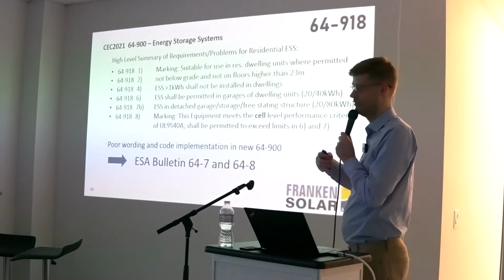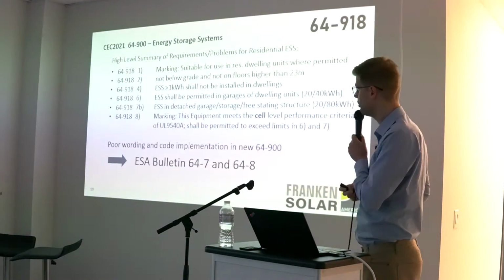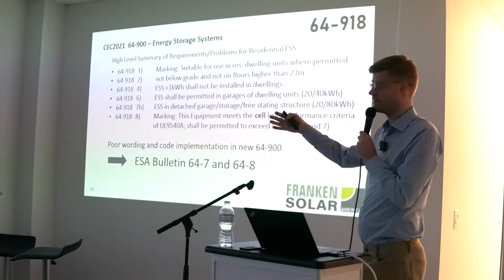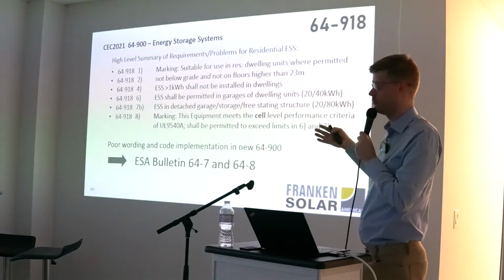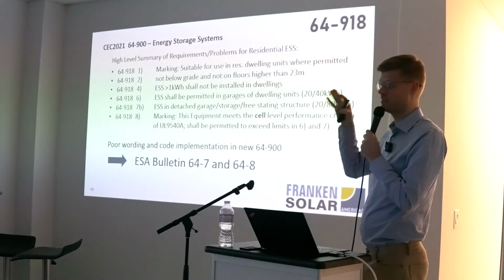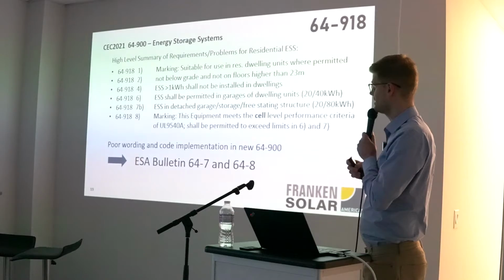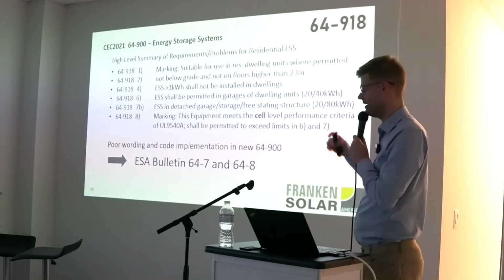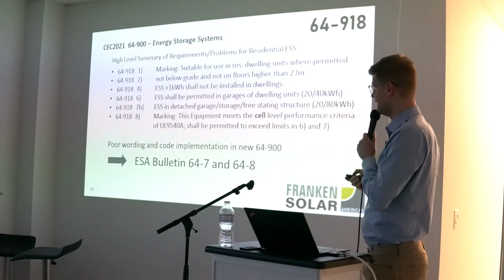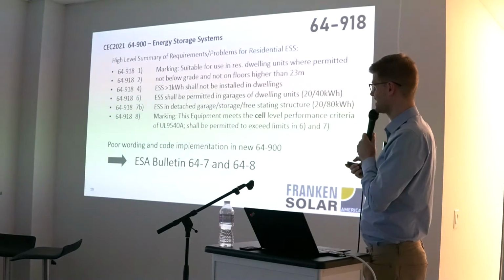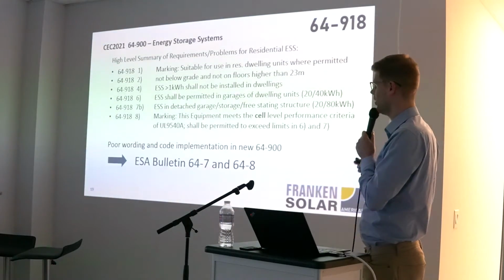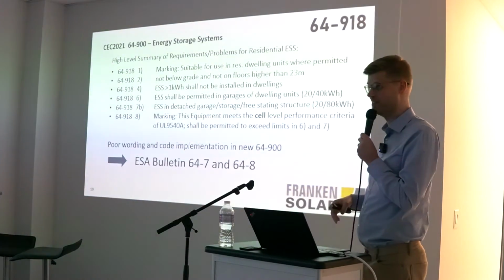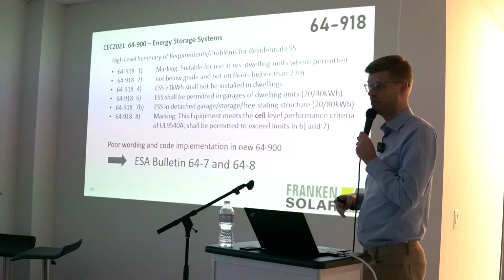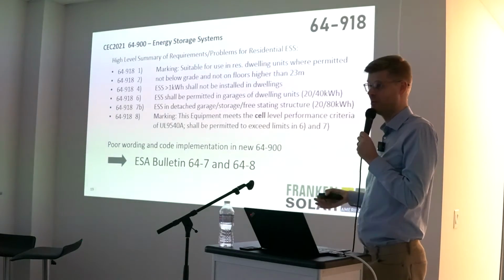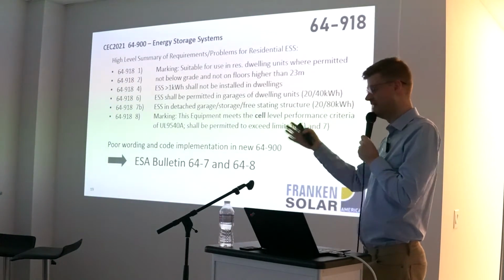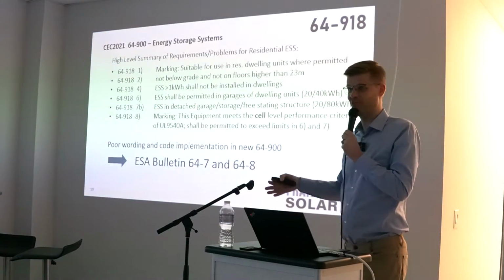The reason for that comes from a firefighter point of view. They typically, with their ladder trucks, maybe can reach higher if you're in Toronto, but if it's the regular city, 23 meters is probably the highest height. They want to address these systems, and they don't want to go into a basement to address a fire in a basement for energy storage systems. It gets worse. Energy storage systems above 1 kilowatt hour shall not be installed in a dwelling. So that's the death sentence if we just read that to begin with, because you can pretty much not do anything. You can get a little UPS system that is based on lithium to power your router, but anything meaningful cannot be installed.